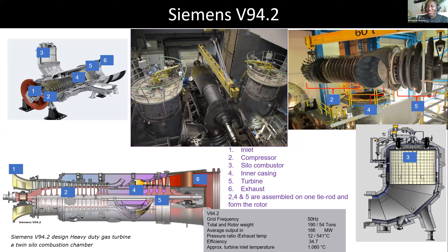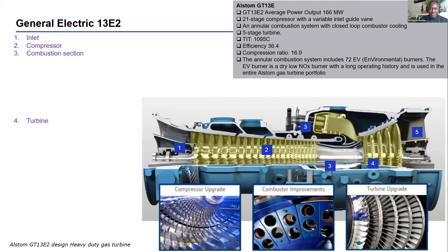Then this is the Alstom GT13E2, which is the most robust, most efficient one, and produces more power. You see, the efficiency is about 36%. It's a turbine with a 21-stage compressor and 5-stage turbine. And this one has the annular combustion chamber. The rotor of this turbine is a welded rotor. It's welded steel, completely welded. It's not like the one for GE or Siemens where you have different discs, but this is a welded rotor. So you can only disassemble the blades. You cannot unstack the rotor. It's a very rigid rotor.